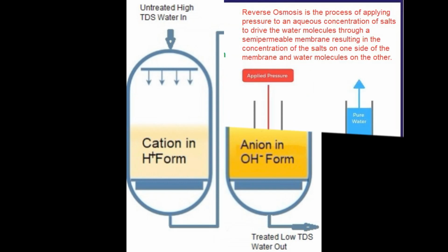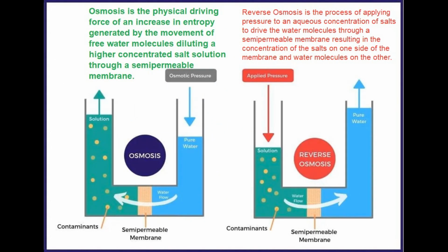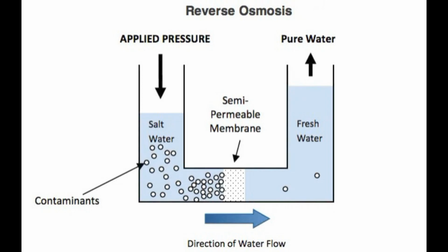Reverse osmosis. This process removes ions using a semi-permeable membrane where water with salts is passed over the surface of the membrane under pressure. The pressure drives the water through the membrane, leaving highly concentrated water with the salt going to waste. This process needs electricity and storage to operate the pumps associated with the process. However, once installed, an RO is an economical method of treating supply water for rinsing surfaces requiring spotless finishes.